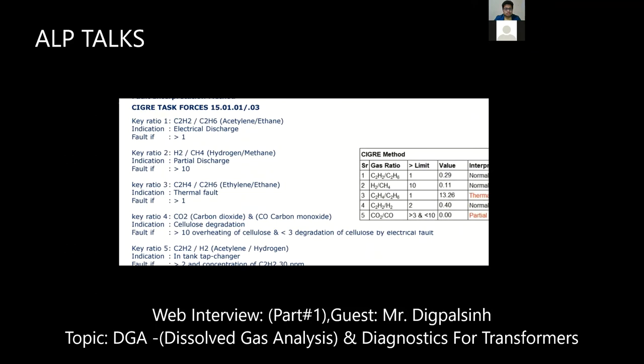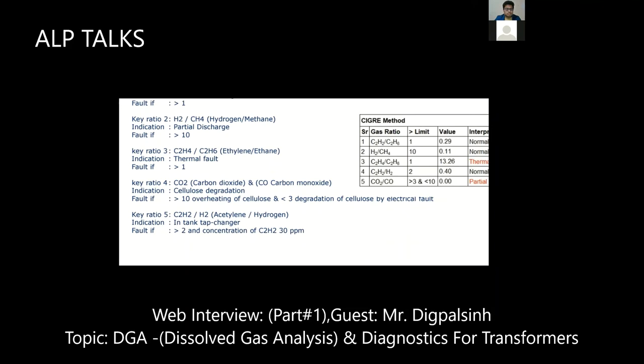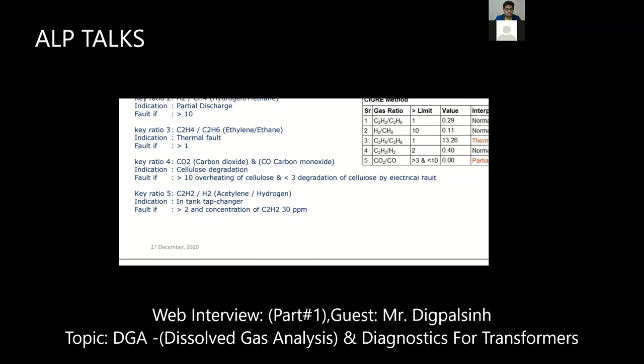So CIGRE tells you electrical discharge is there, but it will not describe whether it is low energy or high energy discharge. For that you have to do further analysis. The second ratio is hydrogen and methane. If this ratio is greater than 10, you can say there is a partial discharge. The third ratio is C2H4 and C2H6, ethylene and ethane. If this ratio is greater than 1, the thermal fault is there. To further categorize whether it is T1, T2 or T3, you have to do some more analysis that we will discuss later on.